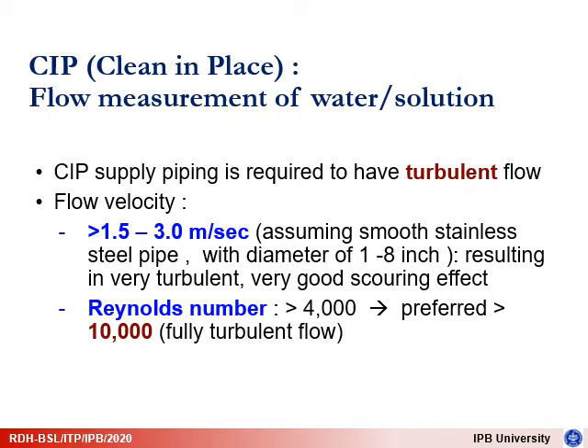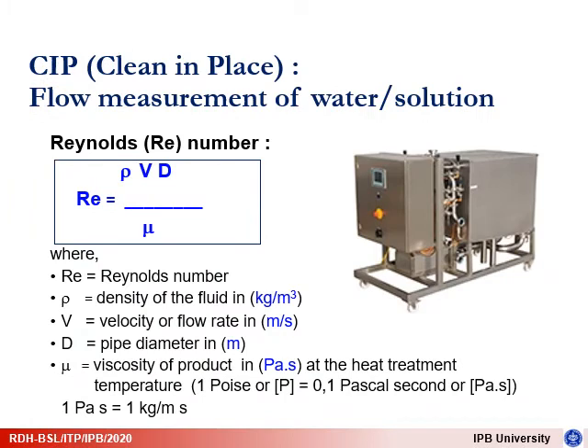The water or solution for CIP requires turbulent flow. For example, with a stainless steel pipe of 1 to 8 inch diameter, a velocity of over 1.5 to 3 meters per second results in a very turbulent, effective scouring effect — or a flow velocity with a Reynolds number over 4,000, preferably 10,000, resulting in fully turbulent flow. The Reynolds number is calculated as: Re = (density × velocity × pipe diameter) / viscosity of the fluid.